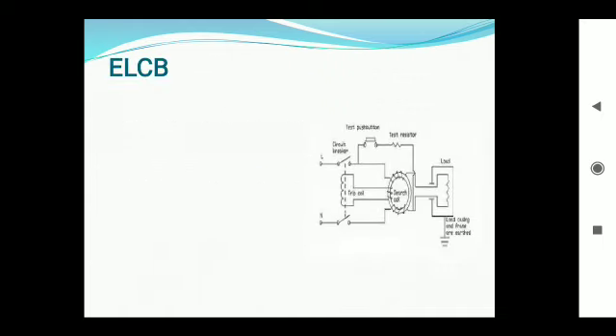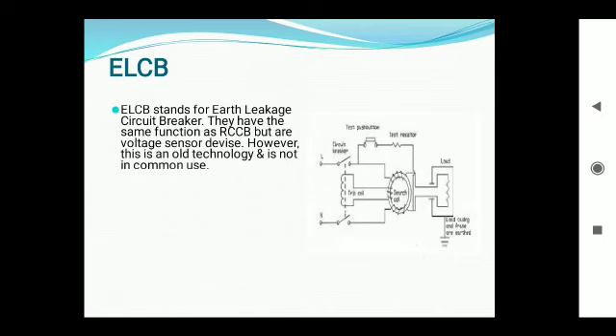Now this is the circuit diagram of an ELCB. You can see the circuit breaker, trip coils, search coil, loads, the test push buttons, test resistors, and the load is earth. ELCB stands for earth leakage circuit breaker. They have the same function as RCCB but are voltage sensing devices. However, this is an old technology and is not in common use.